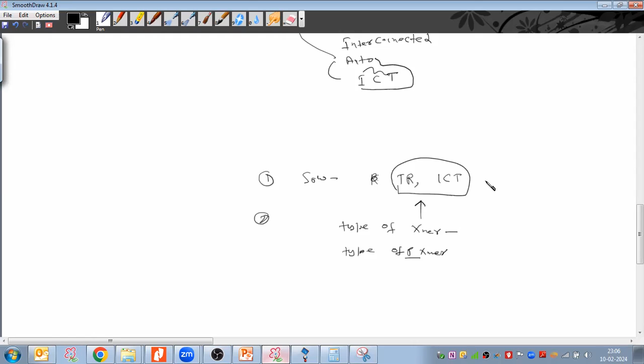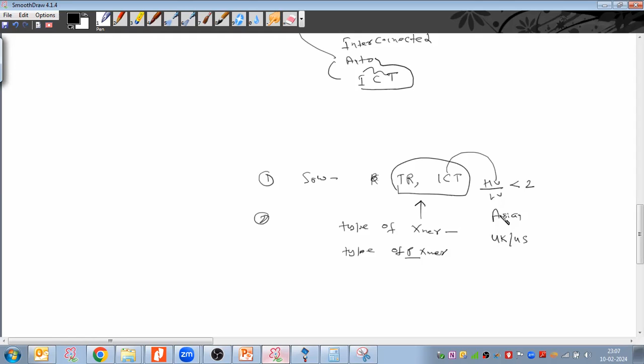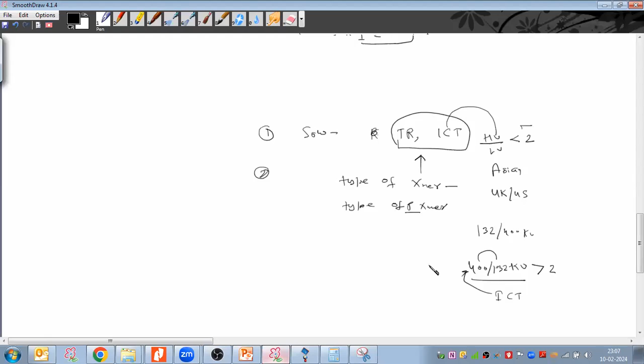What I'm telling is correct for Asian countries, but in the UK and US, they are making substations like 132 by 400 kV, or the reverse, 400 kV by 132 kV. In that case, even though the HV to LV voltage ratio is greater than 2, they are still using ICT, an auto transformer, there. This is correct for Asian countries, but in those countries, for additional cost saving, they go with ICT even at this voltage level.